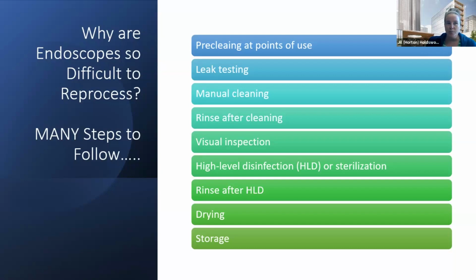So important. If pre-cleaning isn't happening, I'm going to show you some photos in a moment, you'll get things that continue to stay inside the lumens of these scopes, and they can stay in there for a really long period of time. You have to do your leak testing, you have to do your manual cleaning, and you have to do them correctly, and you have to do them every single time. A lot of times we do that quality testing after manual cleaning, which I'll talk a lot about in a minute. We do the rinsing, we do the visual inspections. A lot of borescoping is starting to happen, which I'll talk about again in a moment.